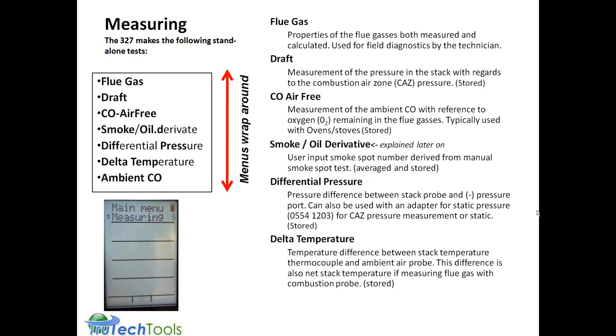Got a question here, is Pascals available in differential pressure? And yes, it is. When we get into the screen setup, I'll show you how you can change that over. And ambient CO, that's just the typical ambient CO measurement in the breathing air. Again, that's a stored value in a special location that'll come up as ambient CO in your printout.